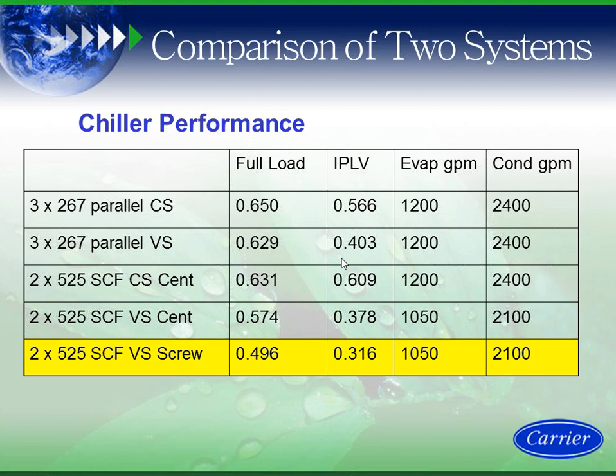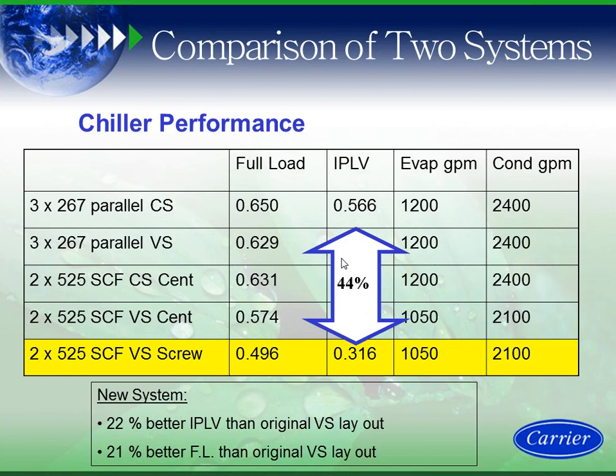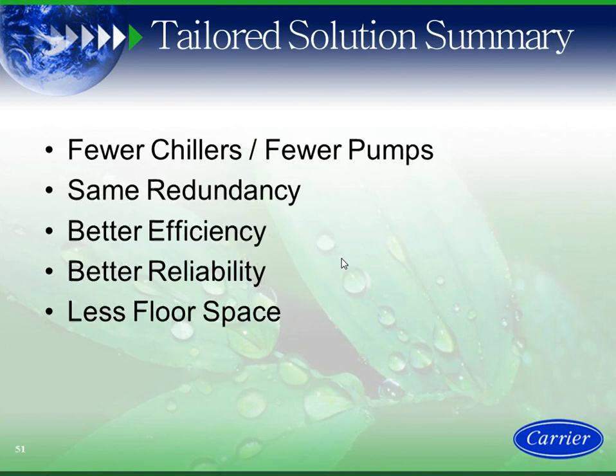But I'm able to reduce the condenser water flow and reduce the evaporator flow on the two 525-ton series counterflow machines. So I'm 22% better than what a lot of engineers would call the best 3 chillers in the marketplace. Okay, and I'm 44% better than the ASHRAE minimums in the marketplace. So 22% and then 21% better than full load.